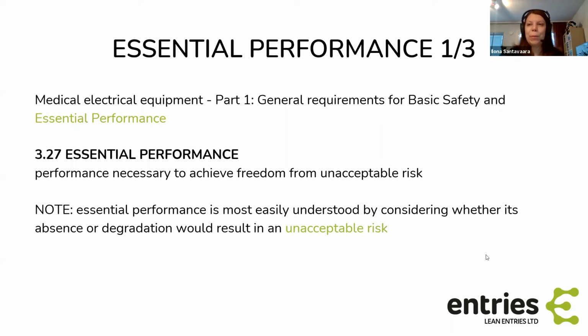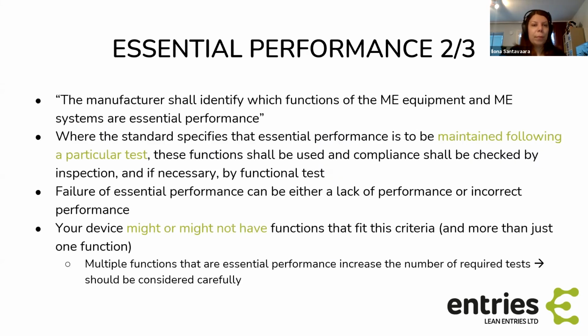Yeah, it's basically performance that is necessary to achieve freedom from unacceptable risk. So that is the definition from the standard. But the standard also acknowledges that this is not a very good definition and says that it's most easily understood by considering whether absence or degradation of this performance would result in an unacceptable risk. So the requirements are that the manufacturer shall identify which functions of ME equipment or systems are essential performance.